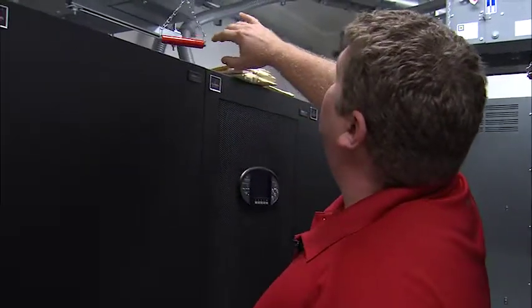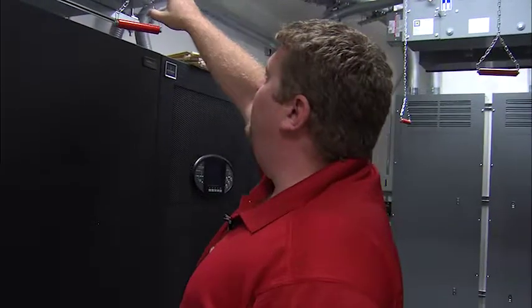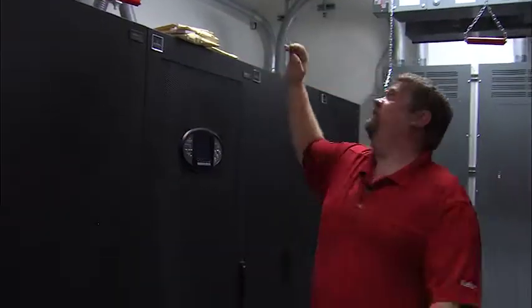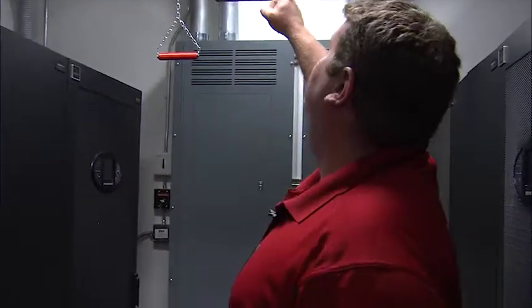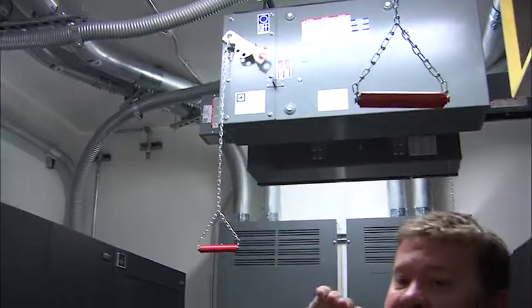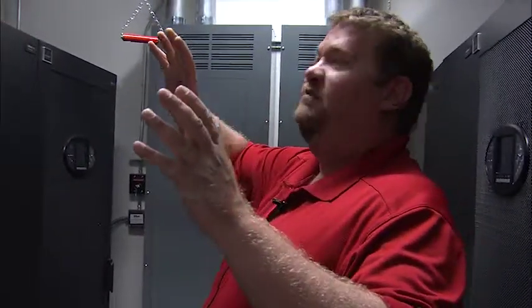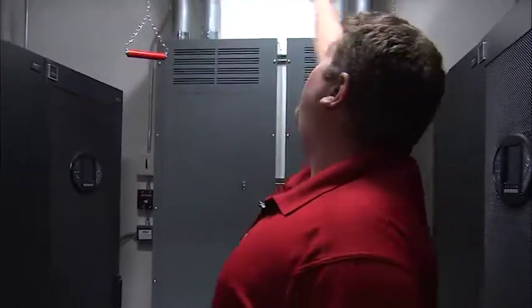You can record this right now, and it's something that Dan and I are working on. These have to be labeled, input and output, and we have that, and we're going to complete that. So right now, our input, we're in bypass. So I would come over here to this one, and I would pull this breaker. At that point, that opens up our output. Once that's done, then we have... No, I'm sorry, let me reverse that. Because they're not labeled, I've got to remember. So this is our input, and this is our output. So we open up this breaker, this one, and this one. That now opens our breakers for our output.